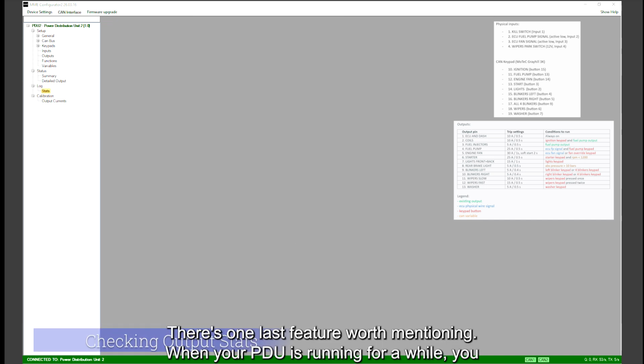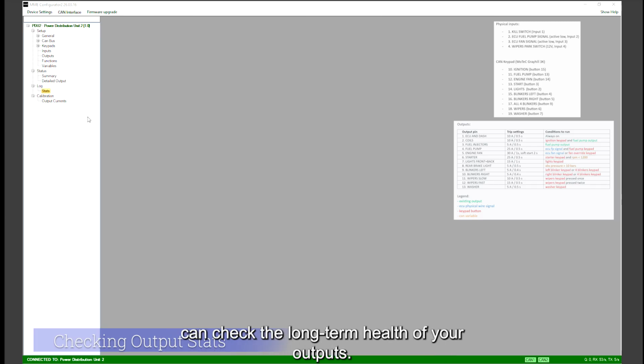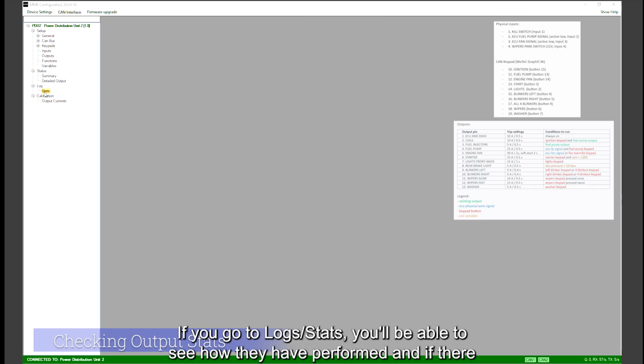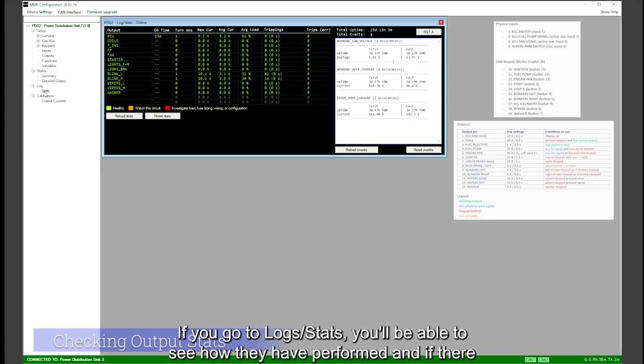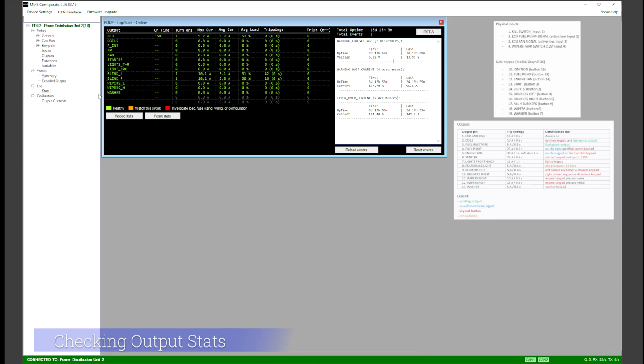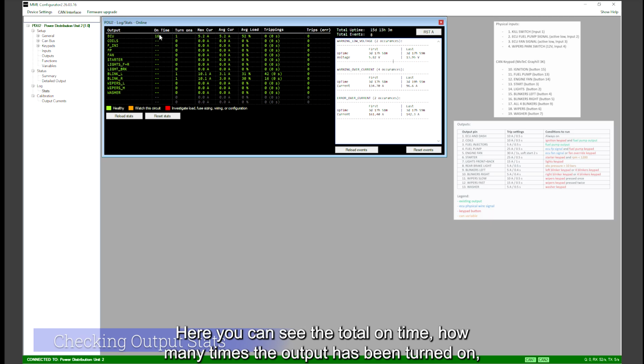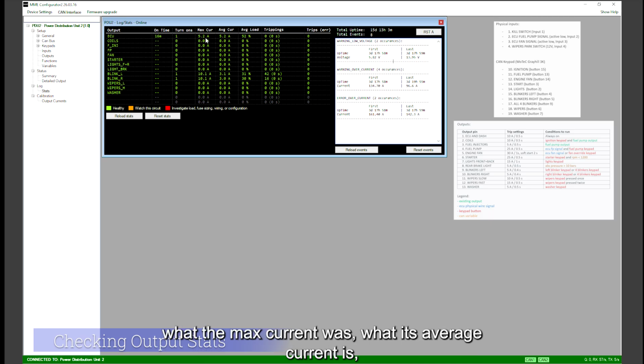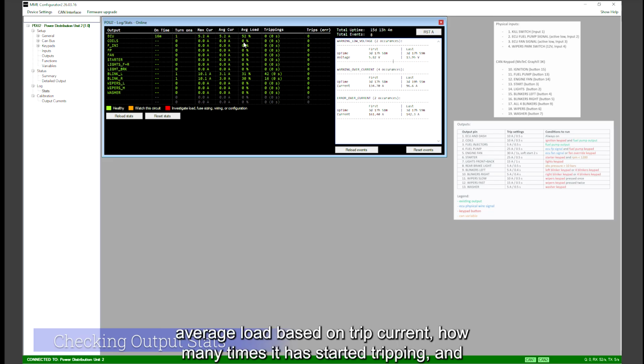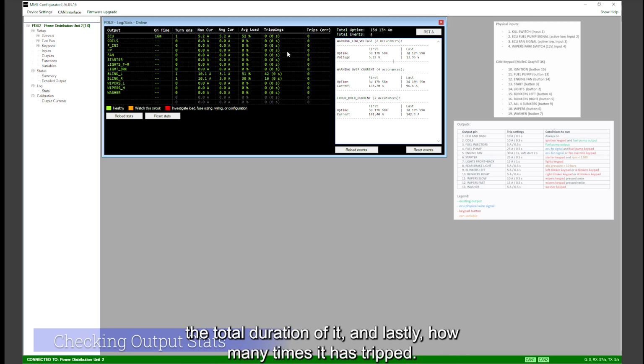There's one last feature worth mentioning. When your PDU is running for a while, you can check the long-term health of your outputs. If you go to logs/stats, you'll be able to see how they have performed and if there are some that need attention. Here you can see the total on time, how many times the output has been turned on, what the max current was, what its average current is, average load based on trip current, how many times it has started tripping and the total duration of it, and lastly, how many times it has tripped.